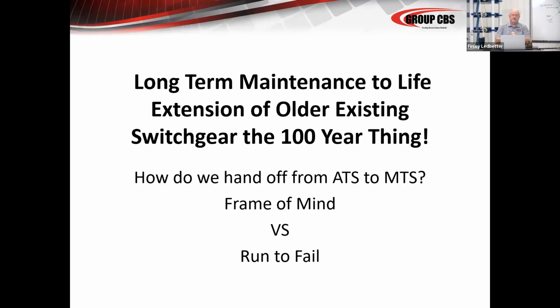Our next webinar will be running into MTS type testing, maintenance testing, and then we'll get into breaker basics and advanced breaker and switchgear testing. So basically what this has been about is what do we do? What do we expect from ATS, and how do we pass that frame of mind and get out of the run-to-fail mentality into maintenance testing?